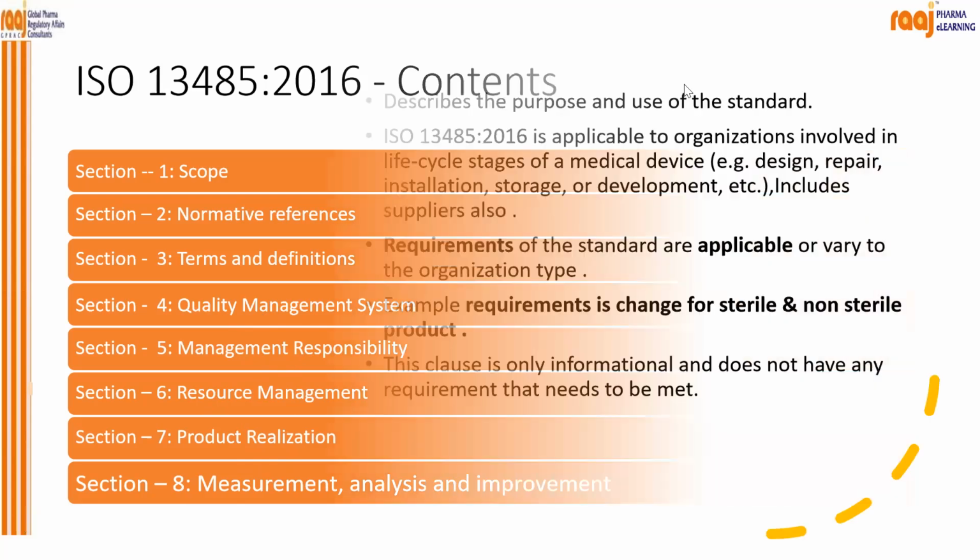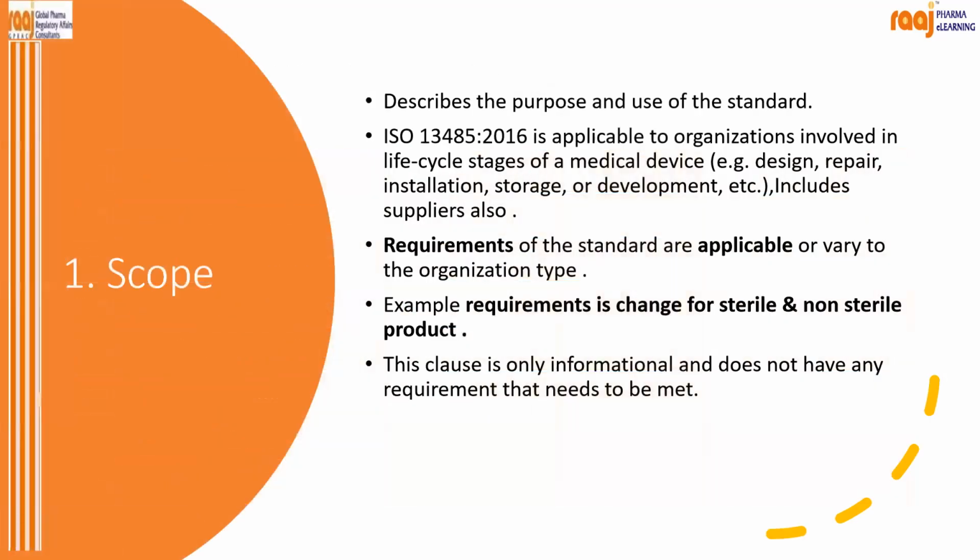Let us start with clause number 1, that is scope, which describes the purpose and the use of the standard. ISO 13485 is applicable to organizations involved in life cycle stages of medical devices. Life cycle means what? Right from design, development, repair, installation, storage, etc. It includes the supplier also, up to the end use.